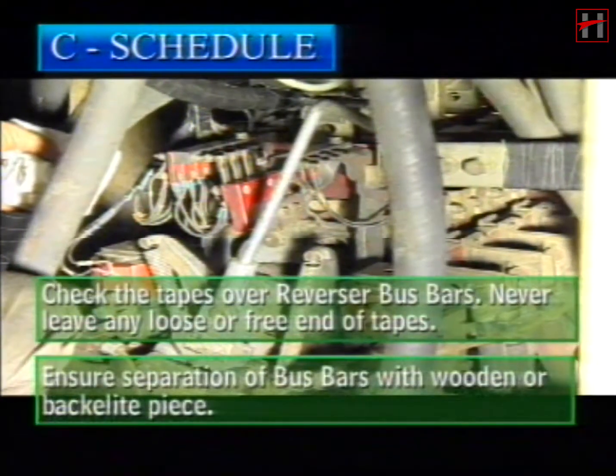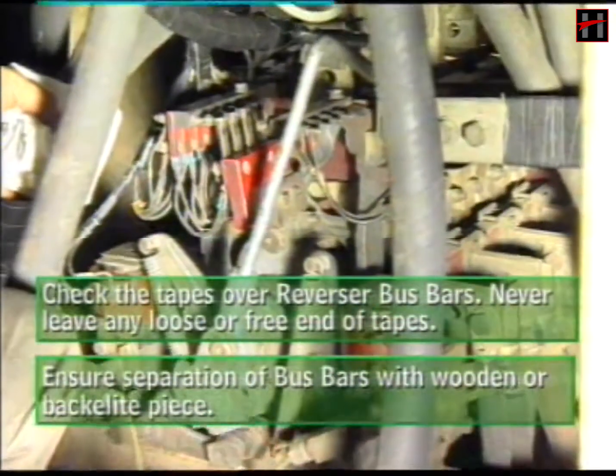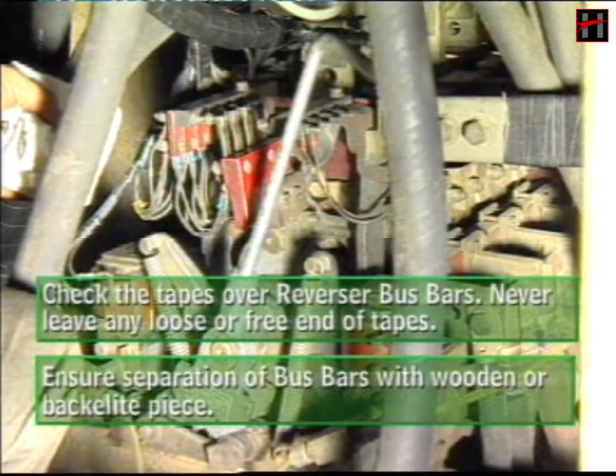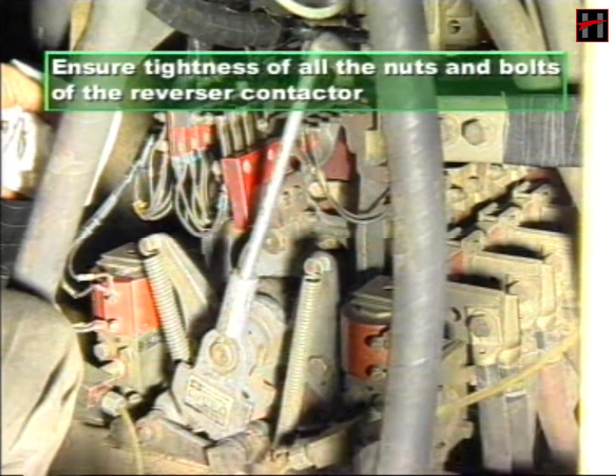Check the tapes over reverser bus bars. Never leave any loose or free end of tapes. Always ensure the separation of the bus bars with a wooden or bakelite piece. Ensure the tightness of all the nuts and bolts of the reverser.